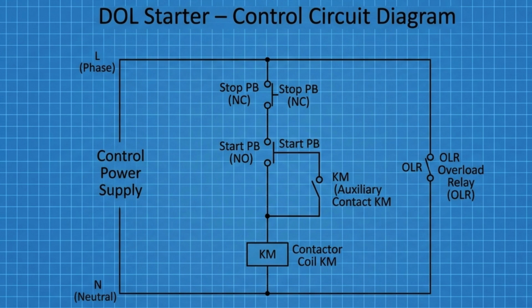Because of this arrangement, even after the start button is released, the control circuit remains energized through the auxiliary contact, keeping the motor running continuously. Another important protection device in this circuit is the overload relay contact, which is normally closed and placed in series with the control circuit. If the motor draws excessive current and the overload relay trips, this contact opens and disconnects the contactor coil, stopping the motor automatically to prevent damage. So in simple terms, the control circuit manages the starting, stopping, and protection of the motor, ensuring safe and reliable operation. In the next part of the tutorial, we will see how the complete DOL starter works step by step, combining both the power circuit and the control circuit together.